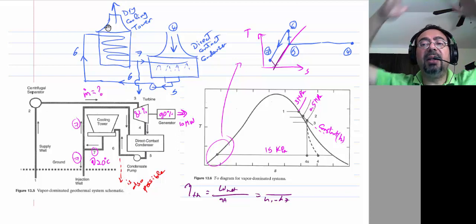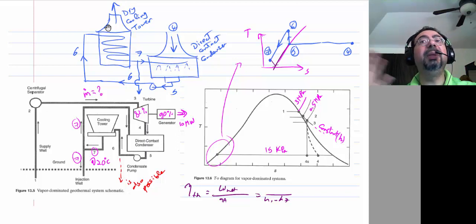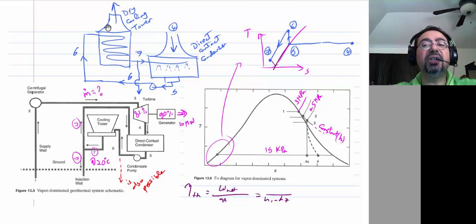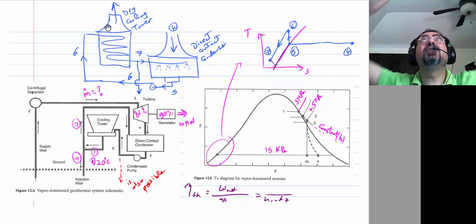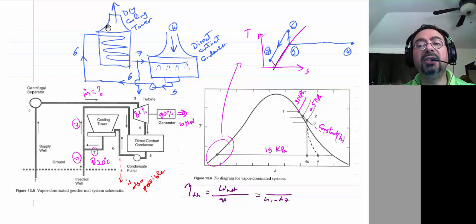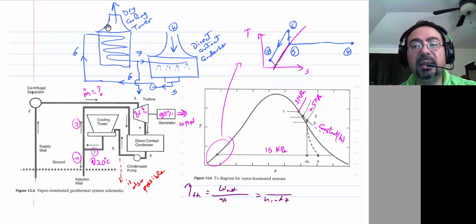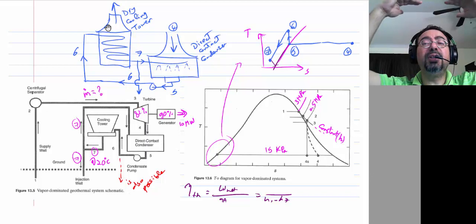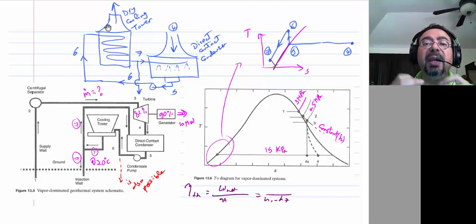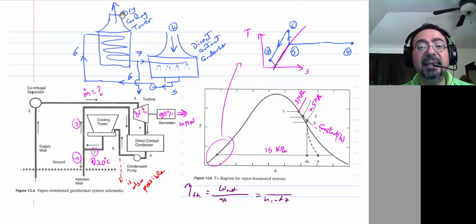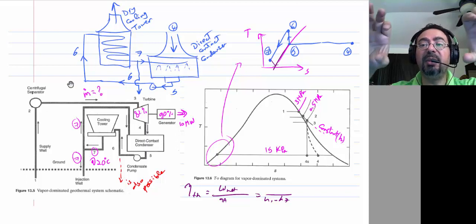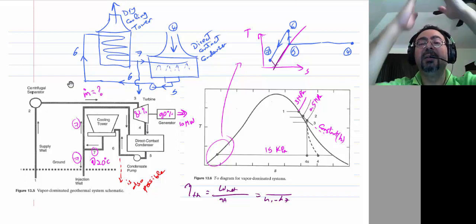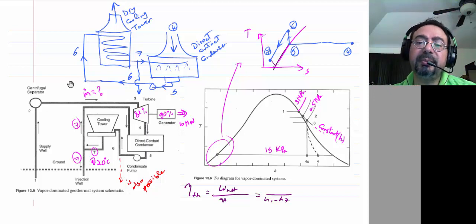The big cooling tower you see in nuclear power plants can be without any fan, using natural convection. Just the fact that the chimney or stack is so high, it will pull the air by buoyancy force. But short ones, like the ones you see in Tulsa, in Jenks power plant for example, or a bunch of power plants we have all over town, those are short. They don't have enough buoyancy force to drive that flow, so they are aided by fans, either at the exit or at the inlet. They put them from the side and let the air go in to basically cool the water.